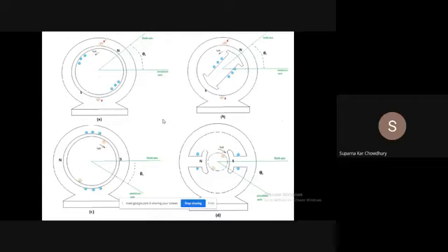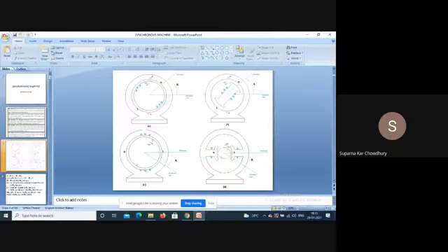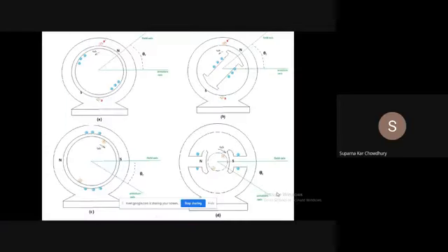On the other hand, if we put the armature on the stator and field on the rotor, that limitation is not there, because the field is a low power circuit. An advantage is that the armature is now a static winding, and it is much easier to insulate it properly, and also easier to cool a static winding than a rotating winding.